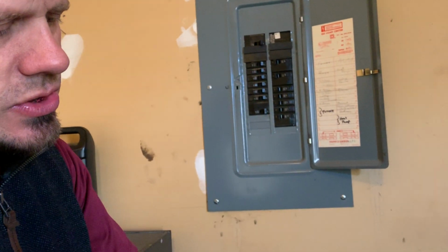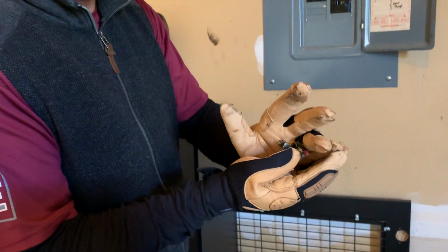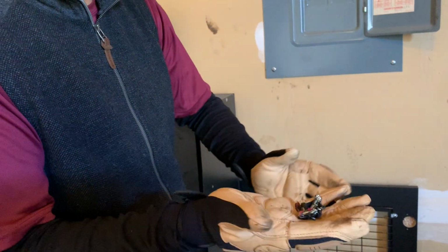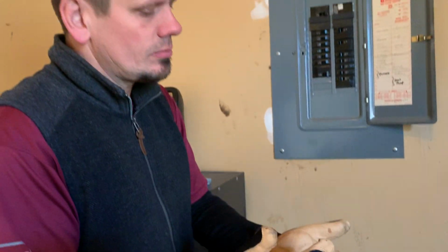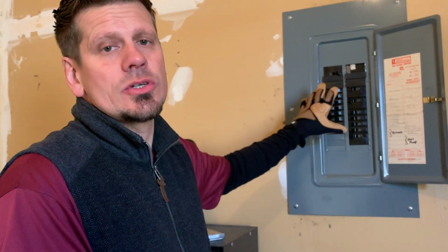So anyways, this is something to keep in mind. We did clean up those breakers. You can get new breakers, but these breakers are rated for aluminum and copper. So you guys on YouTube who love to follow me or give me great criticism and think that aluminum dissimilar metal should have Deox put on the breaker, you are uneducated. You need to stop doing that. You will wreck the breaker, eventually wear out her bus bar, and now she needs a whole service change, or the person you're servicing does. So keep that in mind, that the breaker states it. You need to read what it states.